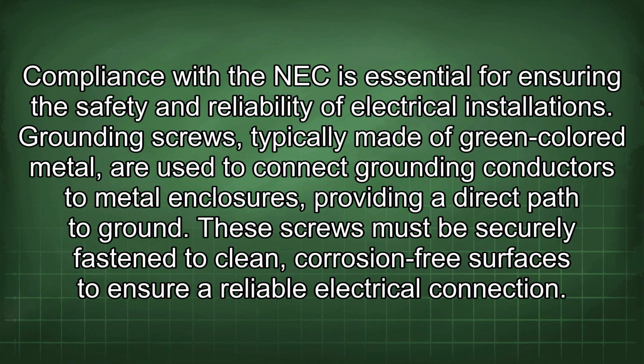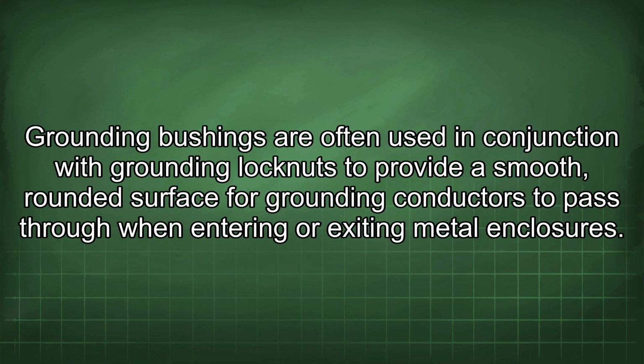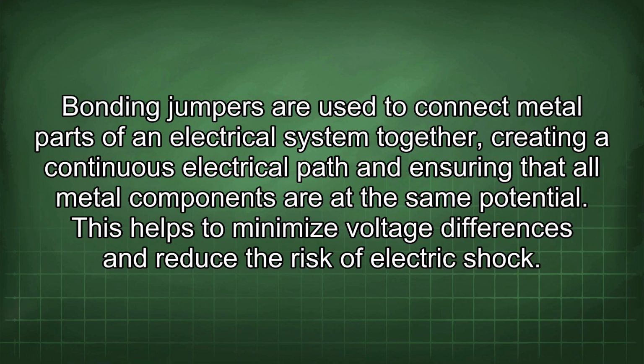Grounding screws, typically made of green-colored metal, are used to connect grounding conductors to metal enclosures, providing a direct path to ground. These screws must be securely fastened to clean, corrosion-free surfaces to ensure a reliable electrical connection. Grounding bushings are often used in conjunction with grounding lock nuts to provide a smooth, rounded surface for grounding conductors to pass through when entering or exiting metal enclosures. Bonding jumpers are used to connect metal parts of an electrical system together, creating a continuous electrical path and ensuring that all metal components are at the same potential.